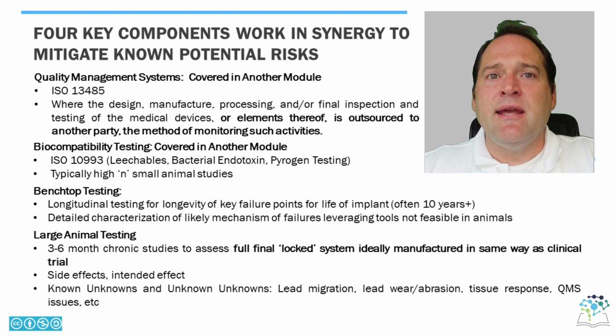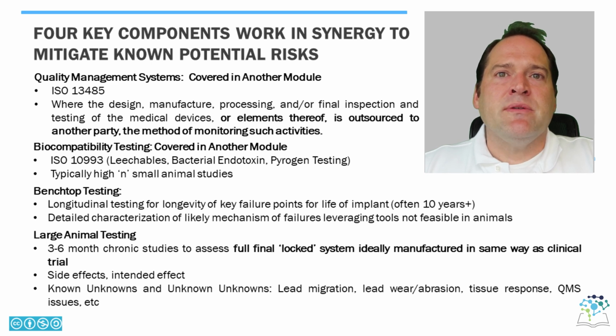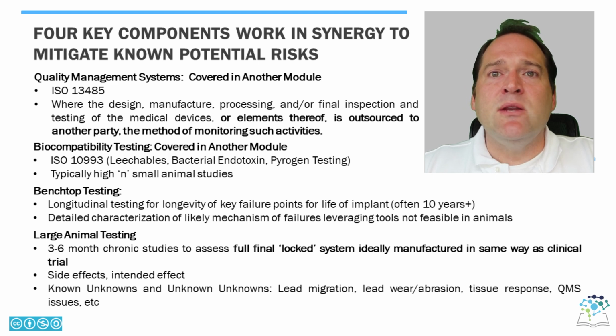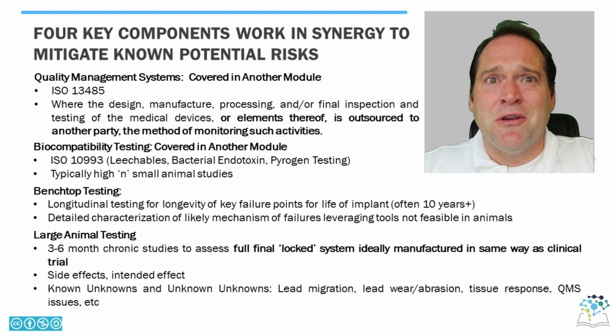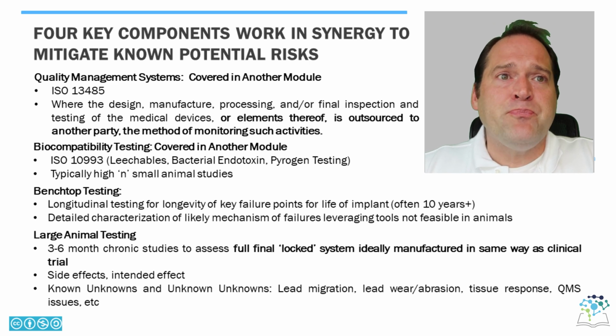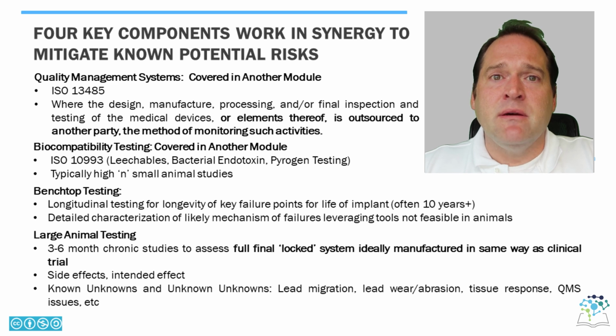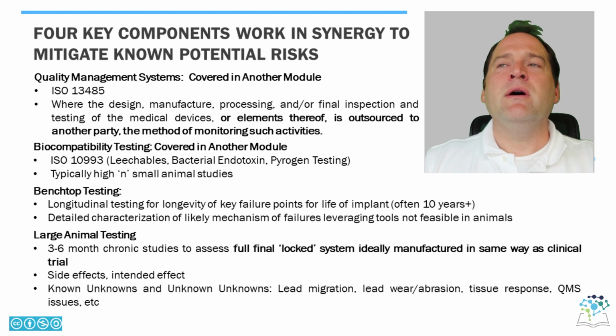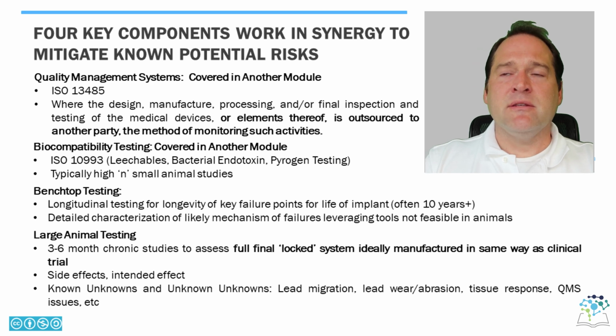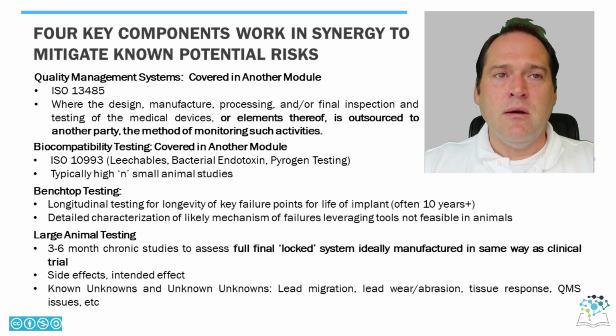You're looking for both side effects and intended effects sometimes, but really this is a sanity check for the known unknowns and unknown unknowns that you can't identify simply through benchtop testing. This is looking at things like lead migration as a function of implant, lead wear and abrasion, tissue response, QMS issues, and several other things that anybody who's done a lot of large animal studies will know they tend to uncover. But you're still not recapitulating 10 years of wear and tear. Realistically, because of the costs of all of these things, the large animal testing tends to be 3 to 6 months and tends to be somewhere in the range of 6 to 8 animals. And the benchtop testing really does a lot of your projection of how well this will survive the lifetime of 10 years and yet still be reasonable for you to do in terms of cost and time.